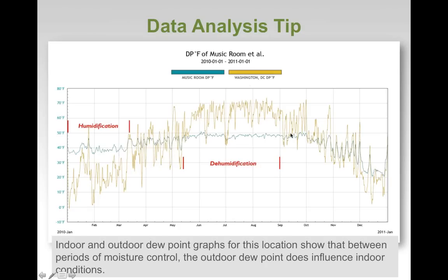And then you have your dehumidification. But after that, unlike the previous graph where this would continue on, you actually notice that it drops off. So there you see there was an influence. There was maybe a system malfunction or something causing no humidity to be added to this air at this point.